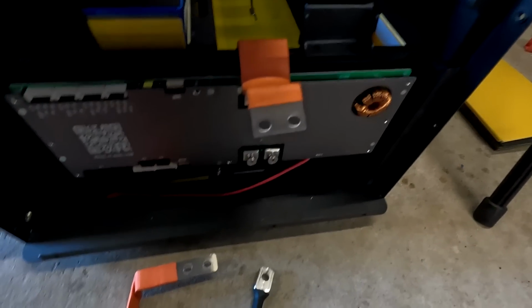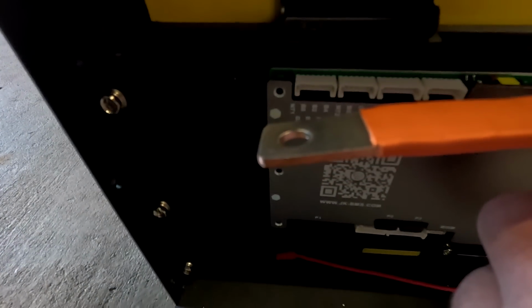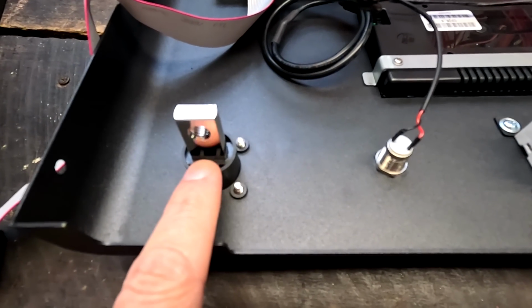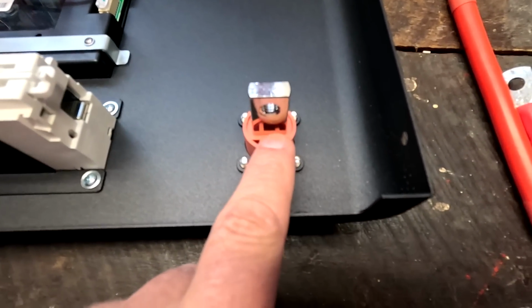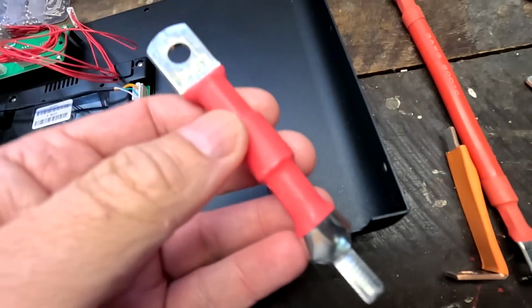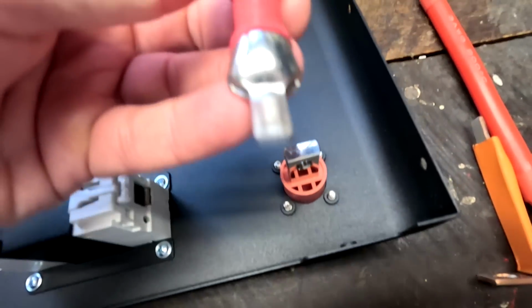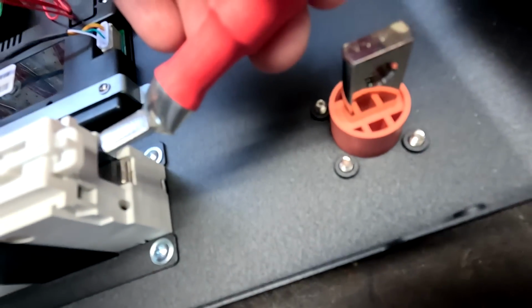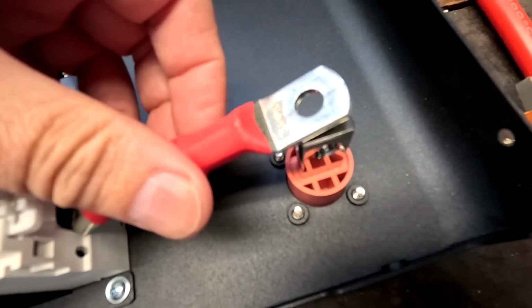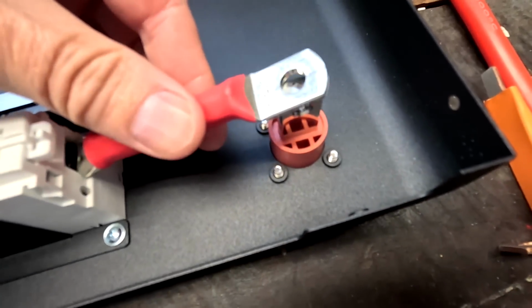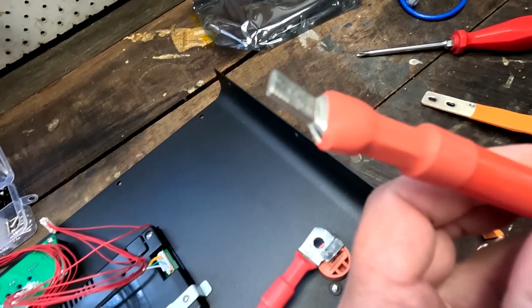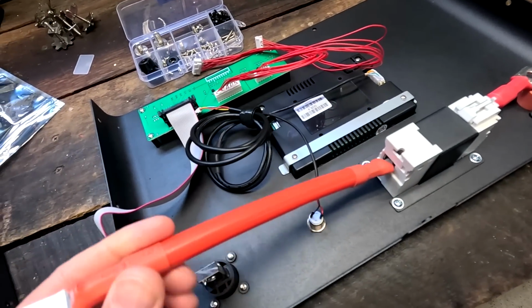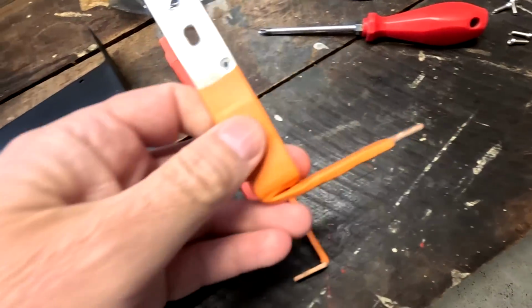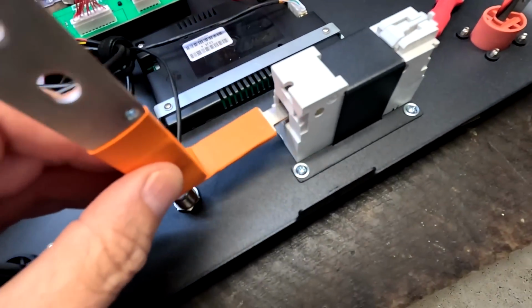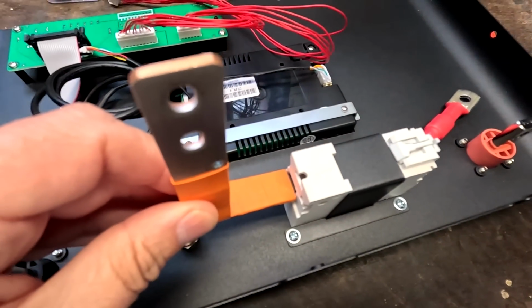So we have this one for the main negative, and this one connecting to the P- of the JK BMS, with the other side connecting to the negative terminal of the box. We installed this terminal the right way, but on the other side, I think the positive needs to be mounted sideways. The box came with this small connection cable with a funny looking lug on one side going into the circuit breaker, and the other side connects to the terminal once twisted 90 degrees. They also supplied this connection cable with the same flat lug for the circuit breaker, which is supposed to connect to your positive battery terminal. But here as well we've got an alternative: we can use this folded flexible bus bar that sits in the circuit breaker, and this one connects to your battery.